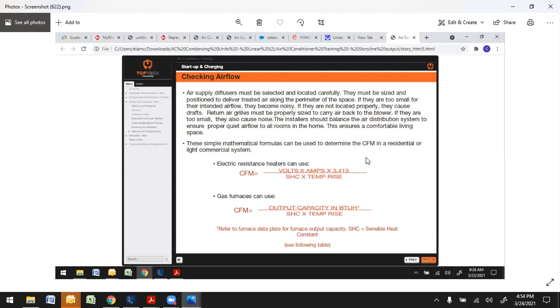But you can also determine what your airflow is. If you have an electric furnace, you can determine your CFM using your electrical resistance heaters. What is your voltage to the unit, to the heaters? Check the amperage, the actual running amperage of all the elements. Multiply that by 3.413. Divide that by your sensible heat constant, which is typically, at our level, 1.08 times the delta T of the system. Delta T being the difference between the supply and return temperatures. Then you divide those two, and that will give you your exact system CFM.